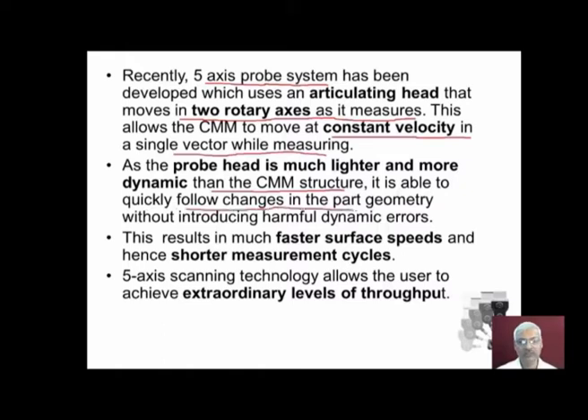Recently, 5-axis probe systems have been developed, which use an articulating head that moves in 2 rotary axes as it measures. That means the 5-axis probe system has additional 2 rotary axes, A axis and B axis, along with XYZ motion given by the CMM structure. This allows the CMM to move at constant velocity in a single vector while measuring. As the probe head is much lighter and more dynamic when compared to the CMM structure, it is possible to quickly follow changes in the part geometry without introducing harmful dynamic errors.